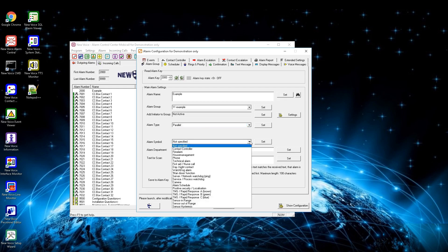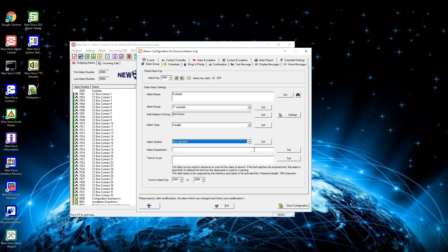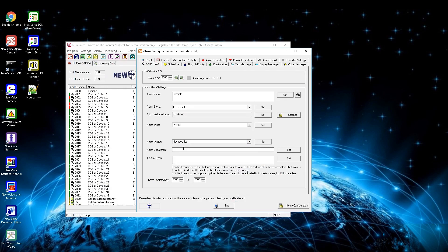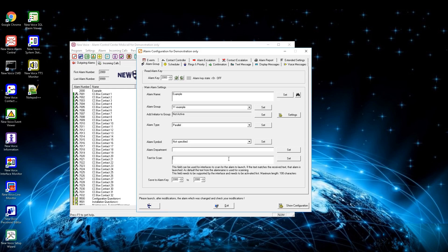In the alarm symbol settings you define what symbol should be shown beside the alarm in the overview, so you can notice at first sight what usage this alarm belongs to. Alarm department needs to be defined for the ACL in web to give users the rights to administrate and view only specific alarms — it must be in the ACL format alarm department. Text for scan is a field where you can enter a text to be scanned for launching alarms from a third-party system; once active, MobiCall won't look in the alarm name for scan anymore and can be activated in the interface.